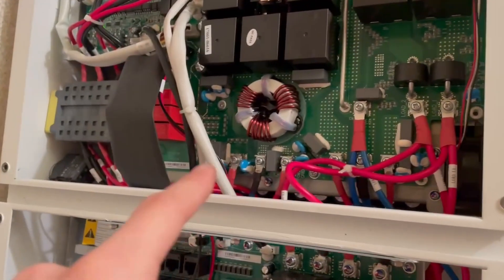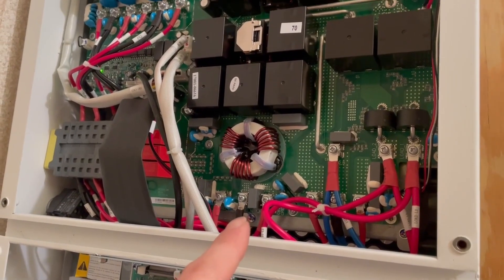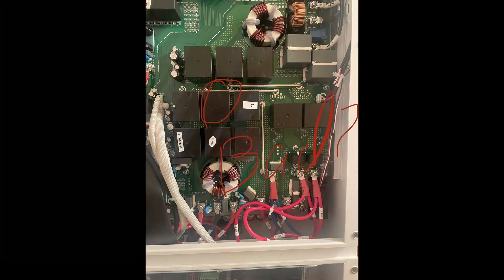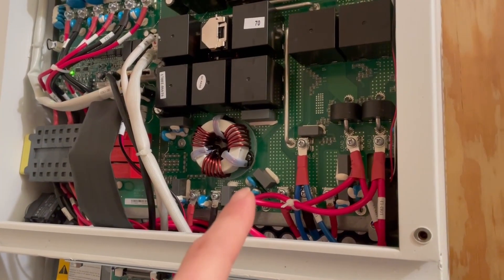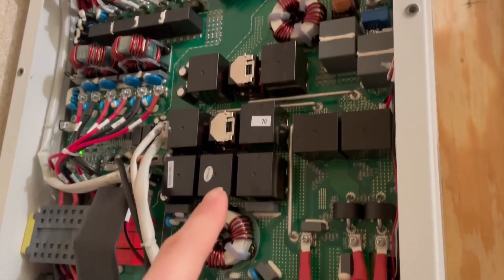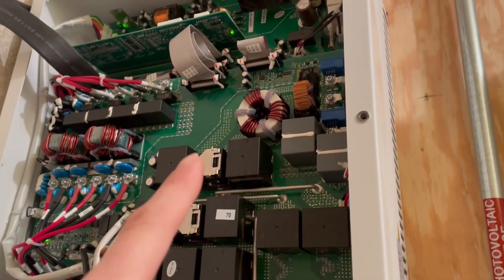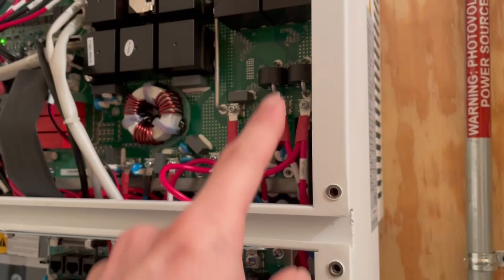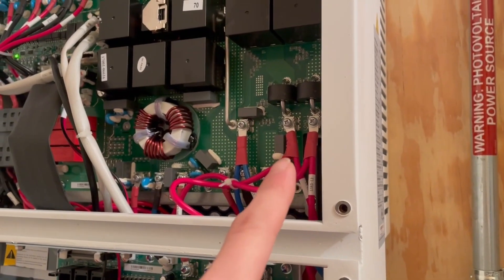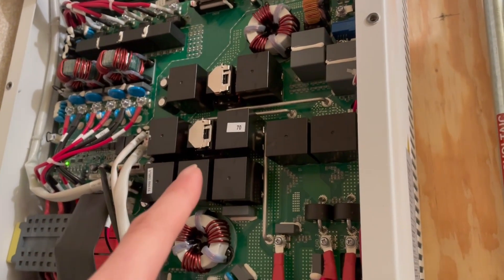I started checking where I had 120 volts versus 240 volts, and I noticed it broke right here at this relay. The grid input goes through here, through this relay, through this relay, through this relay, up to the inverter. Then this line connects to it and goes over to the load output. That relay was not connecting from the top to the bottom.